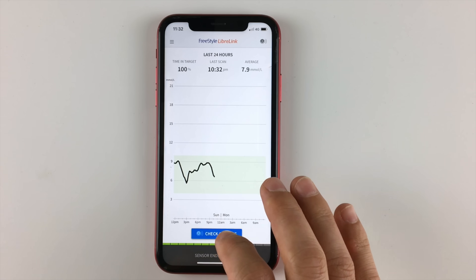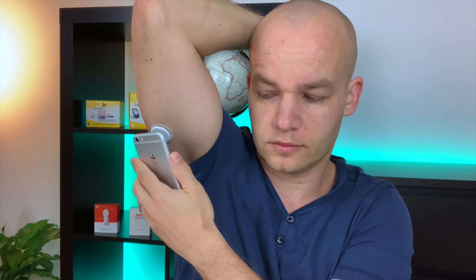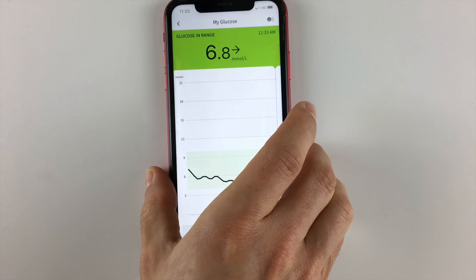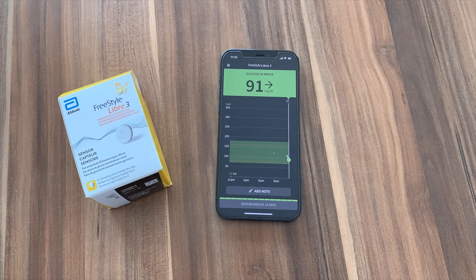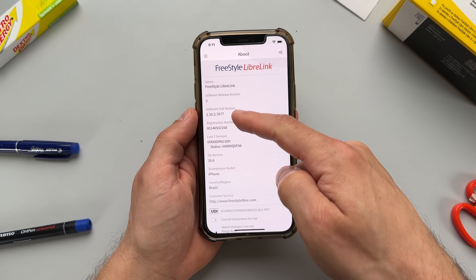Another important Freestyle Libre upgrade is a game changer for those using older versions, but it also applies to those already on Freestyle Libre 3. You no longer need to scan your sensor to see glucose readings, because they are now sent automatically from the sensor to your phone or insulin pump every 60 seconds. This makes everything more real-time, potentially allowing you to act on lows or highs earlier than with any other CGM. Minute-by-minute readings are available by default on Libre 3 and Libre 2 Plus, and you can also get them on Libre 2 by updating the app to version 2.10 or higher.